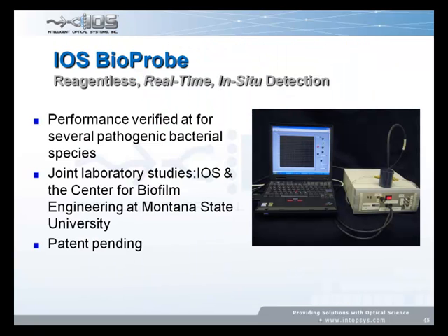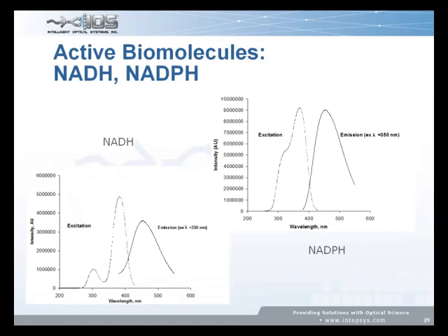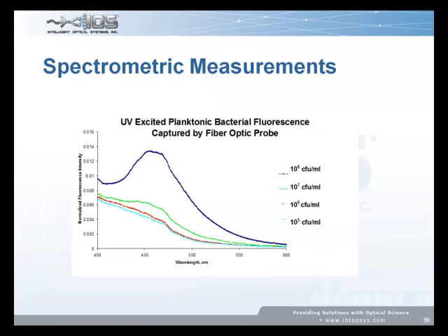So what we really wound up doing was making what I call a life detector. This thing will tell you whether or not you've got live biofilms, and what we're looking at is basically the inherent fluorescence of the NADH, NADPH reaction. If it's going on, then you've got something biological there. And if it's not, then you're okay. So this does detect live biofilms, and bacterial activity doesn't necessarily have to be a film. You can also detect live organisms in solution. It's a relatively simple-minded approach, but it's one that worked quite well for us.